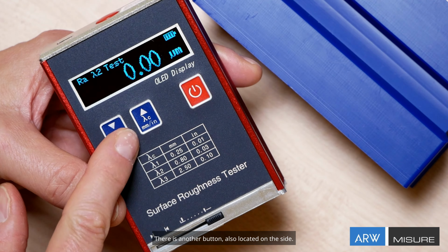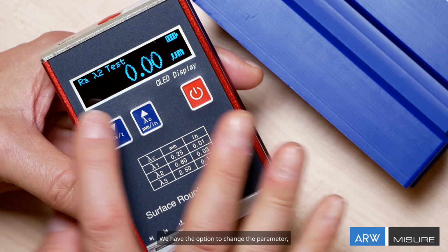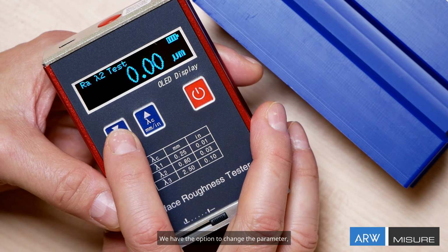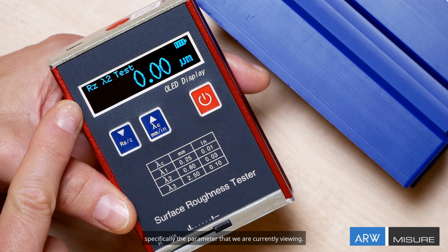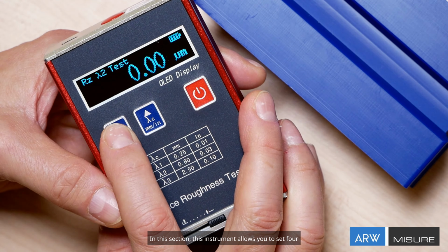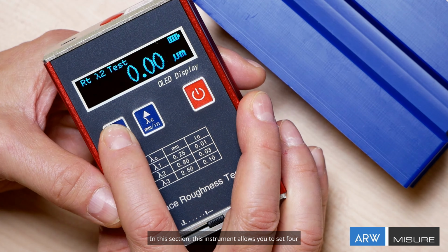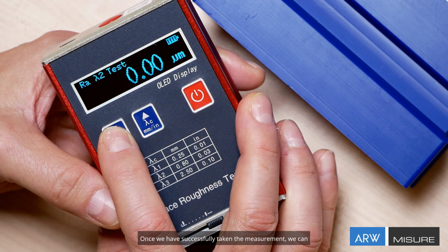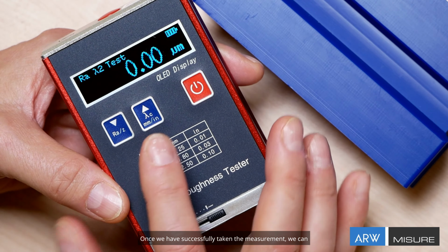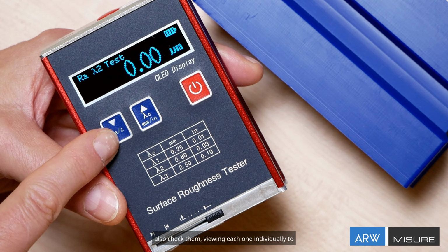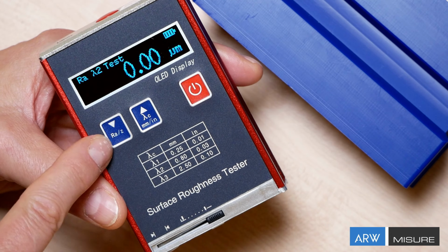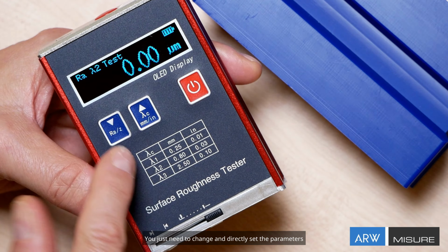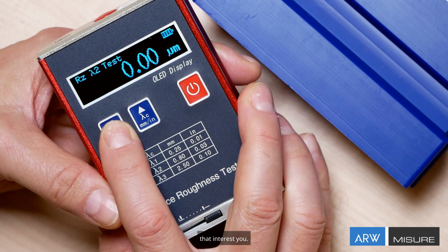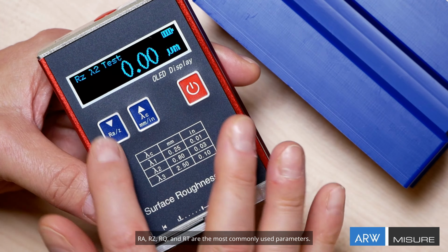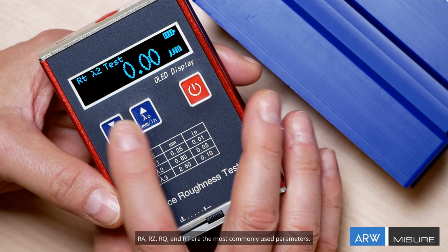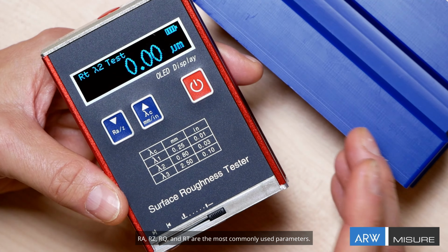There is another button, also located on the side. We have the option to change the parameter, specifically the parameter that we are currently viewing. In this section, this instrument allows you to set 4 different parameters at once. Once we have successfully taken the measurement, we can also check them, viewing each one individually to ensure accuracy. You just need to change and directly set the parameters that interest you. RA, RZ, RQ, and RT are the most commonly used parameters.